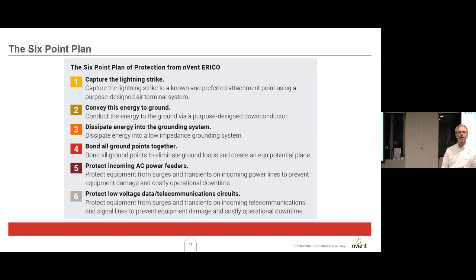The 6-point plan, I'll just run through the points. That's the picture I showed earlier at the beginning of the presentation. Capture the lightning strike, or consider if you do need to capture it or not. And if you do, then work out how you're going to convey the energy to the ground, so what conductors you're going to use and where you're going to position them. Then point 3 is how you're going to dissipate the energy into the ground. So you're looking at your earthing, look at your ground type.